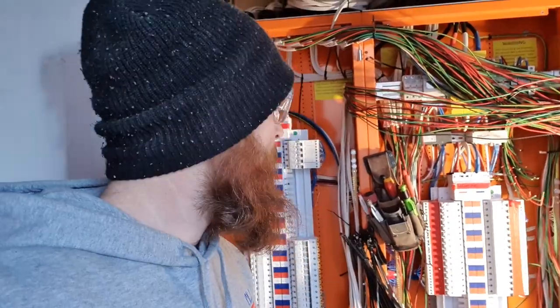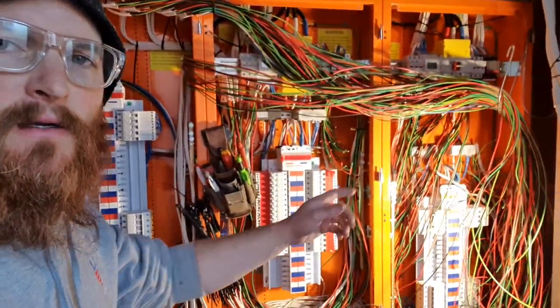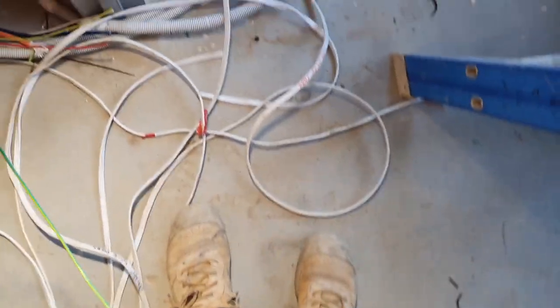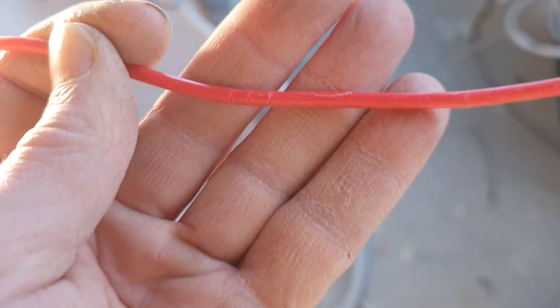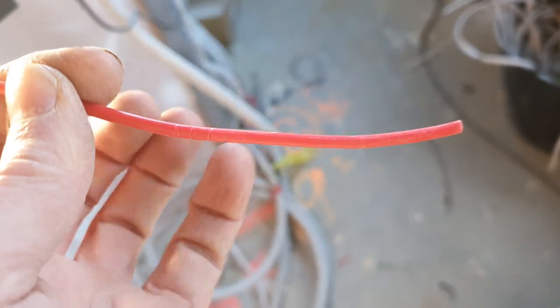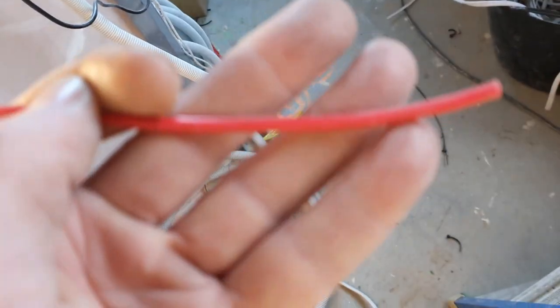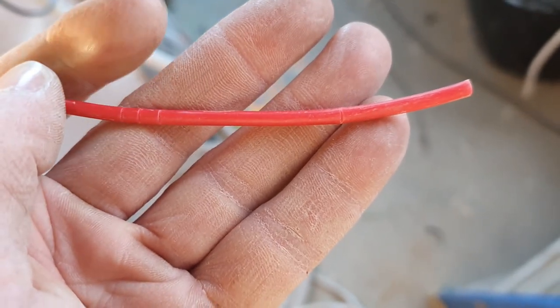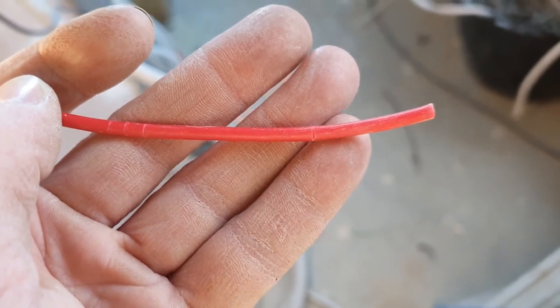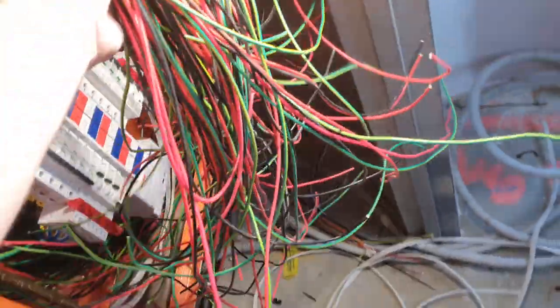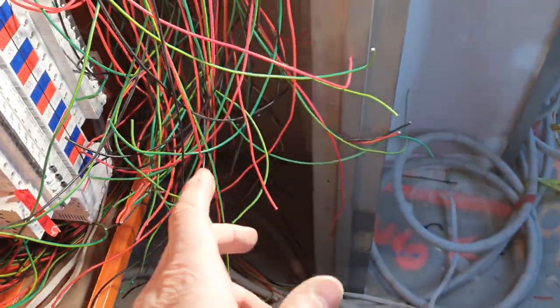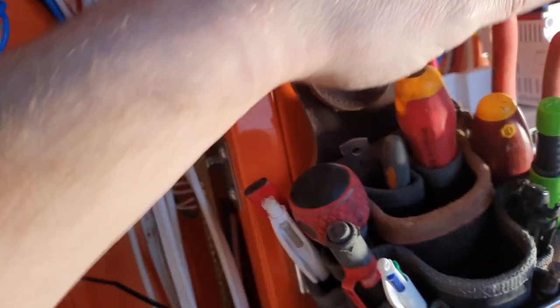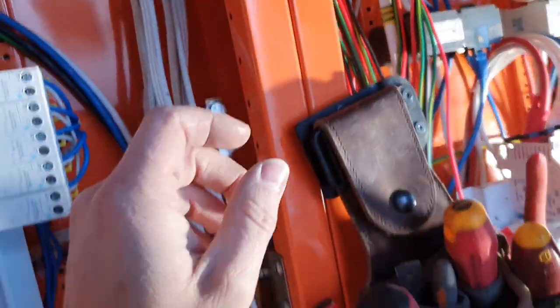Hey everyone, end of the day. Got a good bit done today. Everything's stripped and labeled around. I'll show you my little labeling method. Let me zoom in with it again. All right, so that's how I mark a 31, three and one with a gap. It's heaps quicker than doing tape flags. And basically when you strip the cable, you can just use one tool and you're marking everything up. So I do also mark where I strip, just relabel it just in case, because this is fallible. You can make a mistake and need to redo something. So if you do need to trace it, at least you got the mark there and you don't have to go fucking around out in the field.